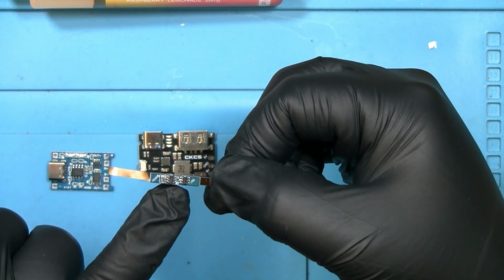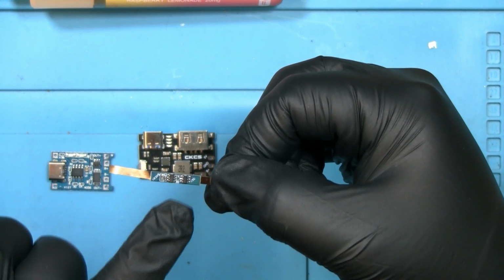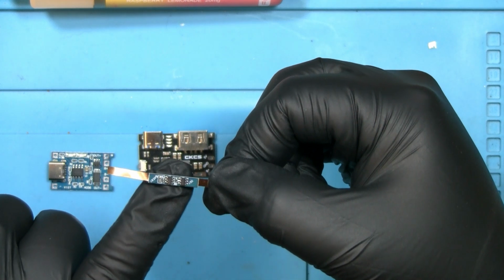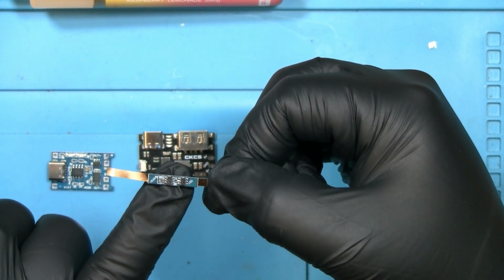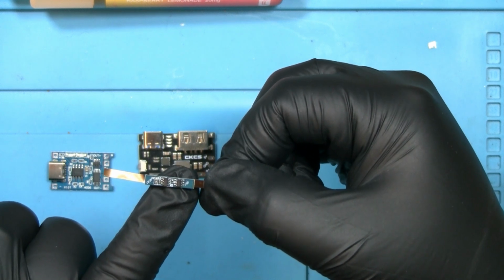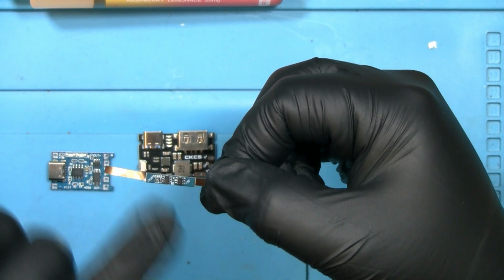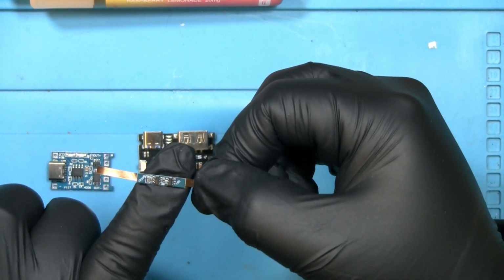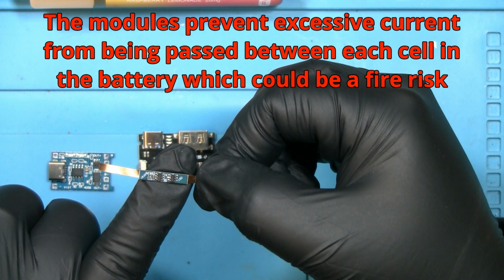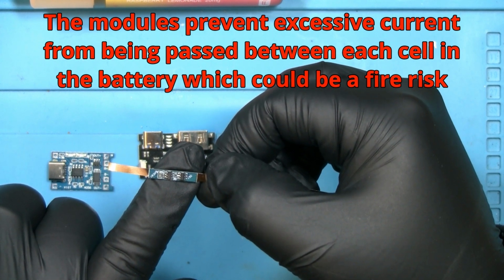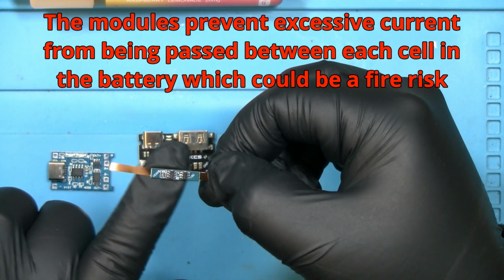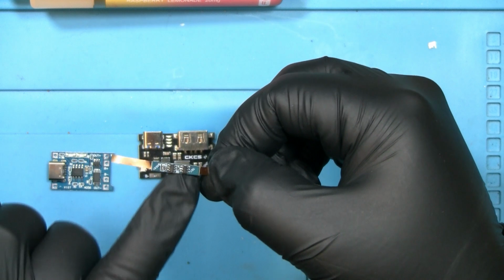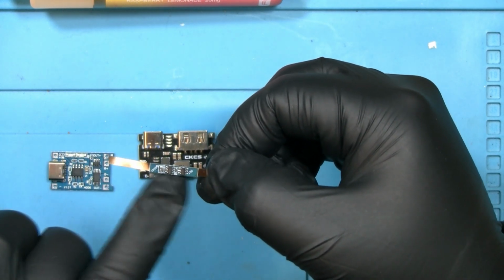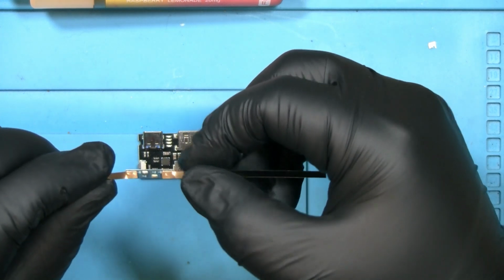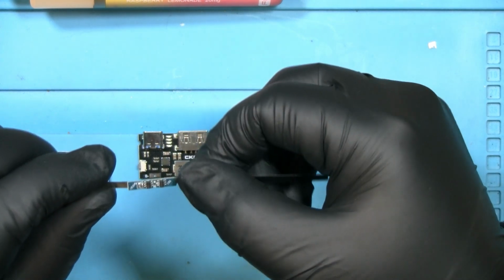These will fit to the batteries as a secondary measure. When the batteries are connected in parallel, these control boards will stop the batteries from being overcharged by each other. Basically, if there's no control, it's like turning a tap on - you can put too much current into the battery between themselves, and it can damage the cell or even set it on fire if you get a thermal runaway. So these devices will prevent that from happening and make the battery inherently safer.